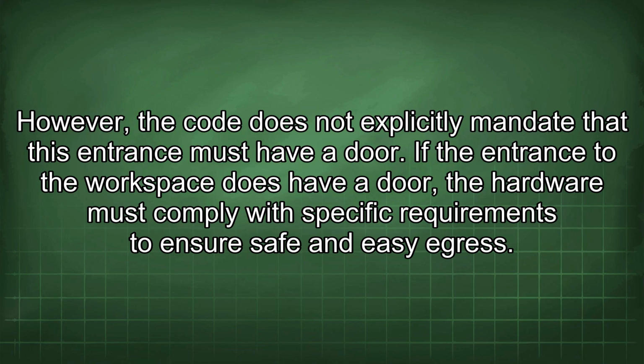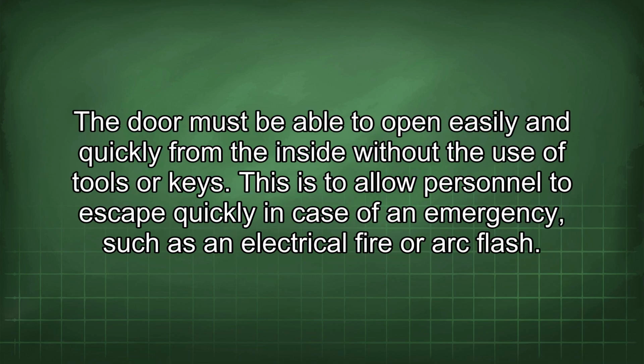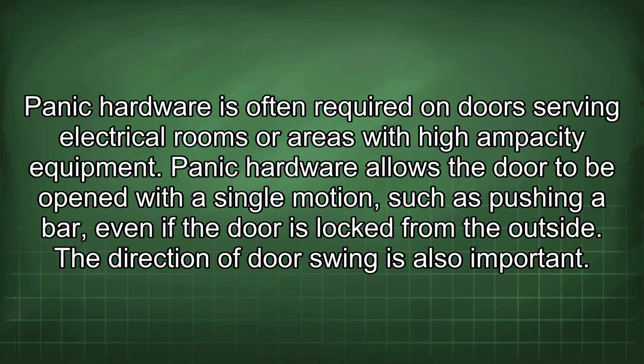If the entrance to the workspace does have a door, the hardware must comply with specific requirements to ensure safe and easy egress. The door must be able to open easily and quickly from the inside without the use of tools or keys. This is to allow personnel to escape quickly in case of an emergency, such as an electrical fire or arc flash. Panic hardware is often required on doors serving electrical rooms or areas with high ampacity equipment. Panic hardware allows the door to be opened with a single motion, such as pushing a bar, even if the door is locked from the outside.